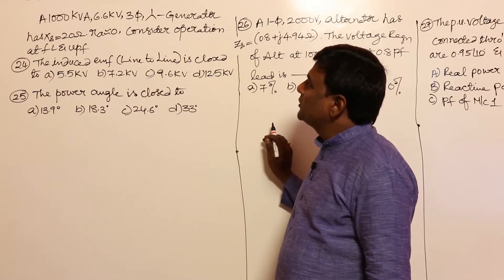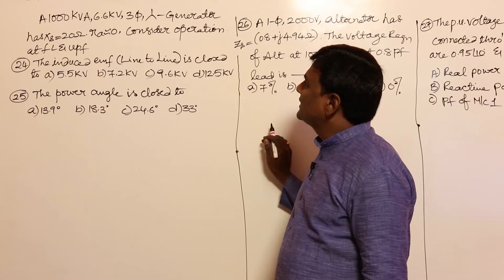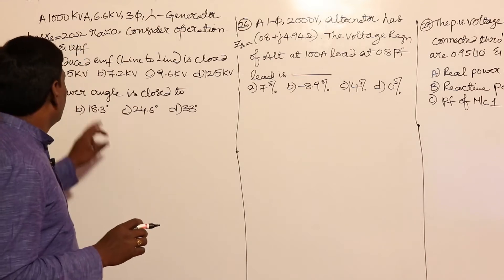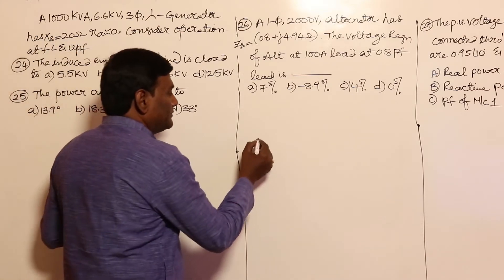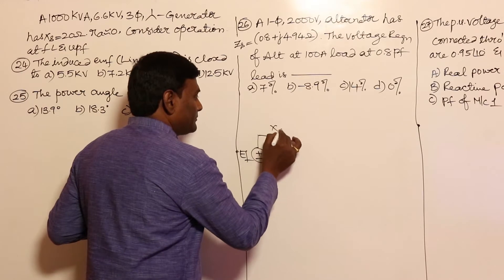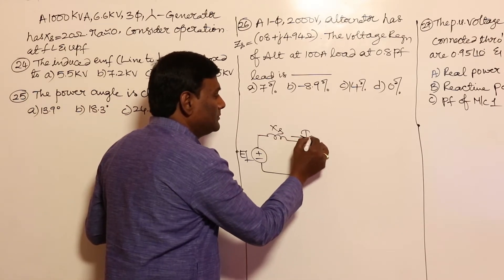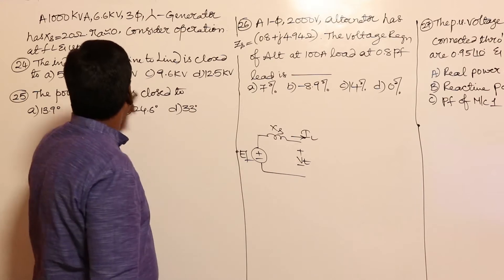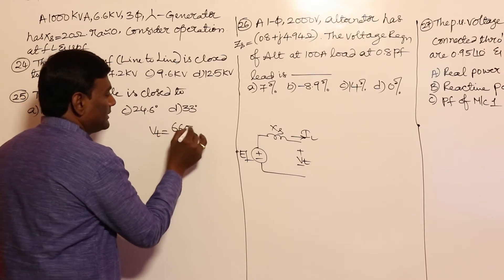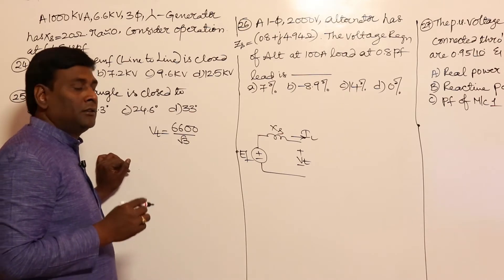A 1000 kVA, 6.6 kV, three-phase star-connected generator has synchronous reactance of 20 ohm; armature resistance is neglected. Consider operation at full load, unity power factor. In an alternator, Vt will be maintained constant independent of the load, so Vt is rated at 6.6 kV line-to-line. Per phase, Vt equals 6600 divided by root 3.